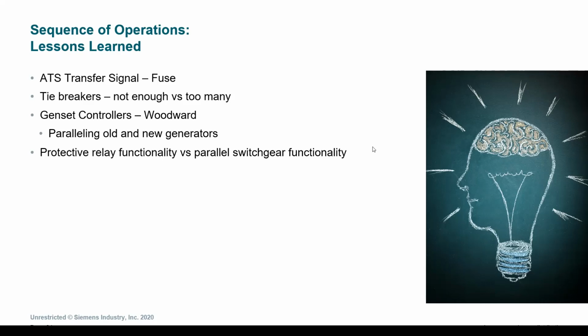Next, on medium voltage systems, relays have a very effective functionality for added resiliency. It's important to make sure that those relays are not programmed in a manner that disrupts or impacts the parallel switchgear functionality and programming. This is usually identified as part of the development of the project, but always important to review on existing facilities.